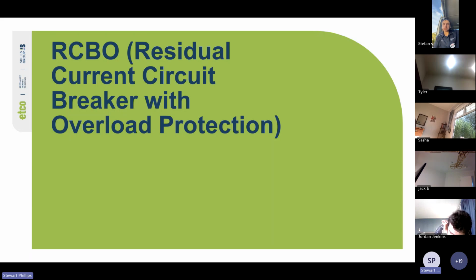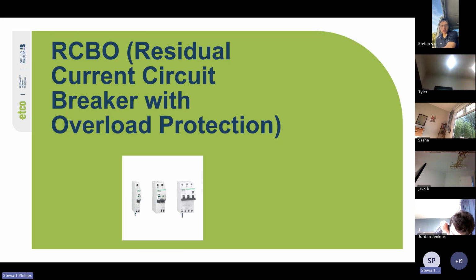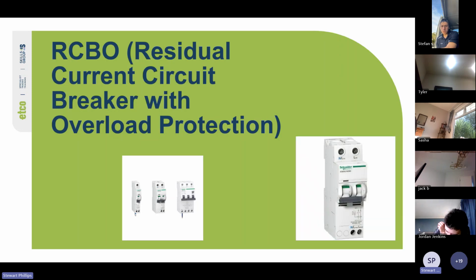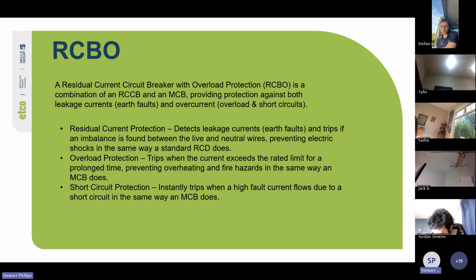And then we start talking about the RCBO, or residual current circuit breaker with overcurrent protection or overload protection. Cool. So there's a few types there. You've got a slim line, double wide, and then that one is a 3-phase on the end there. And that's just a closer look at that middle one there. Cool. So an RCBO, a residual current circuit breaker with overload protection, is a combination of an RCCB and an MCB, providing protection against both leakage currents, earth faults, and overcurrent, overload, and short circuits.